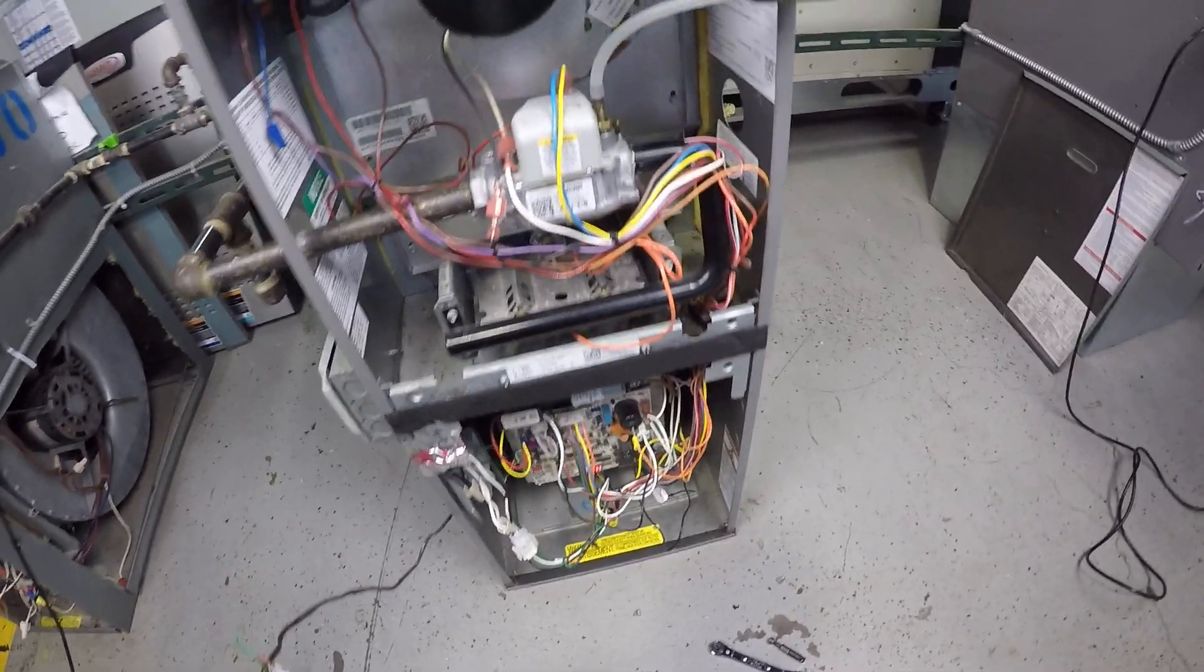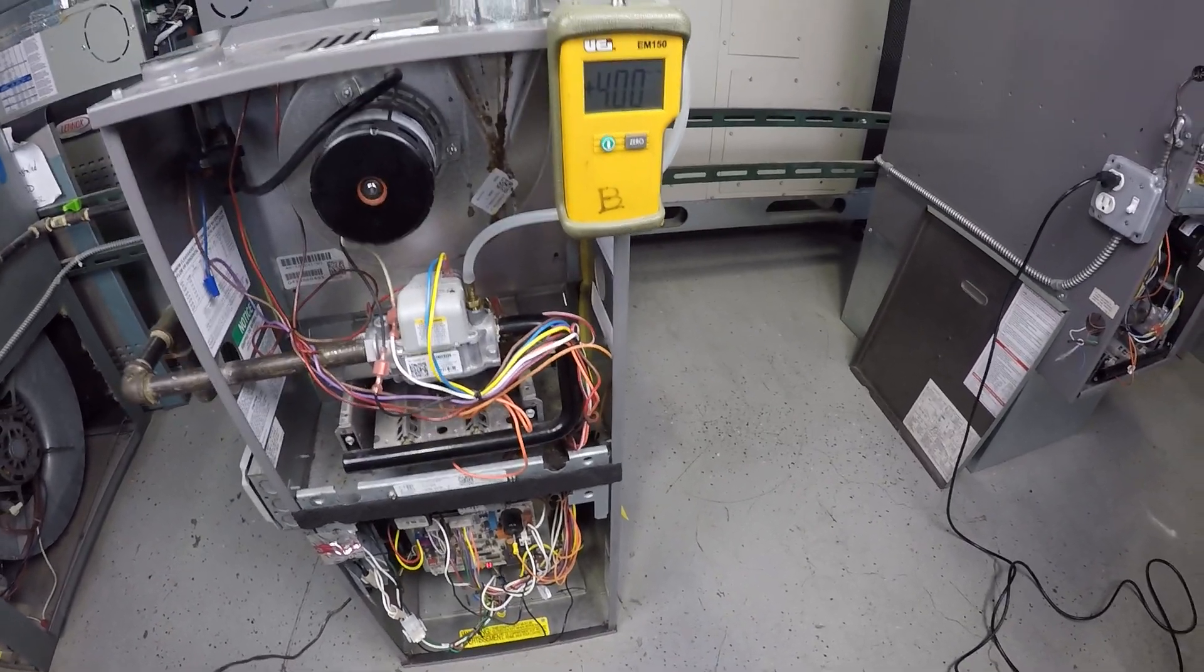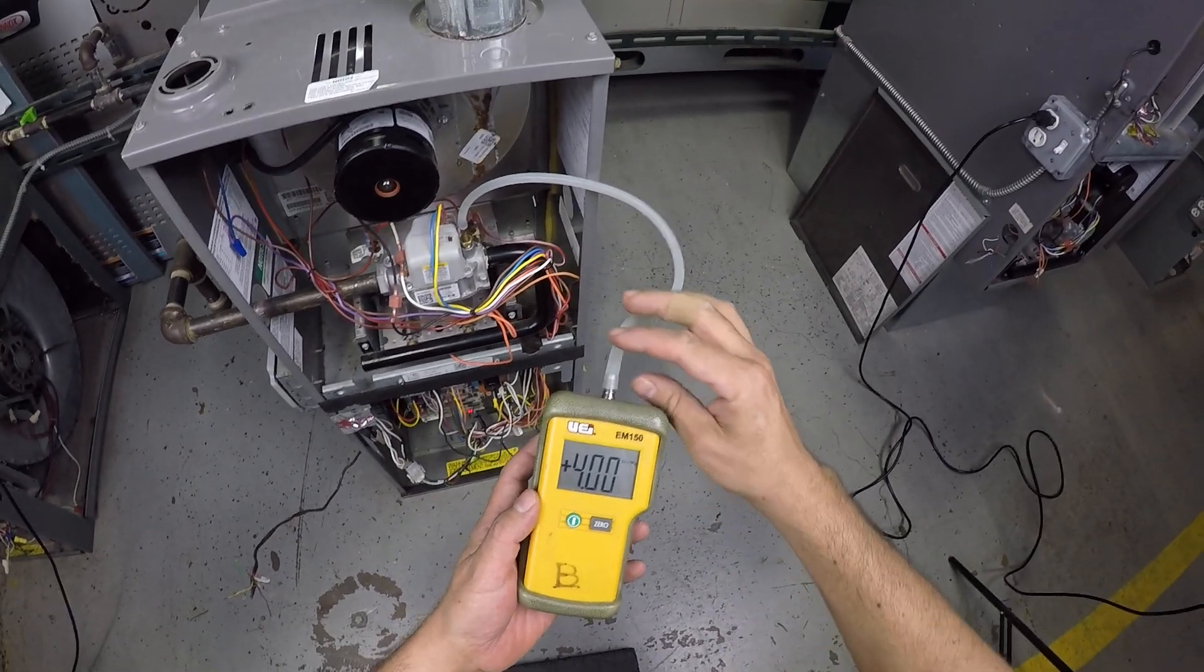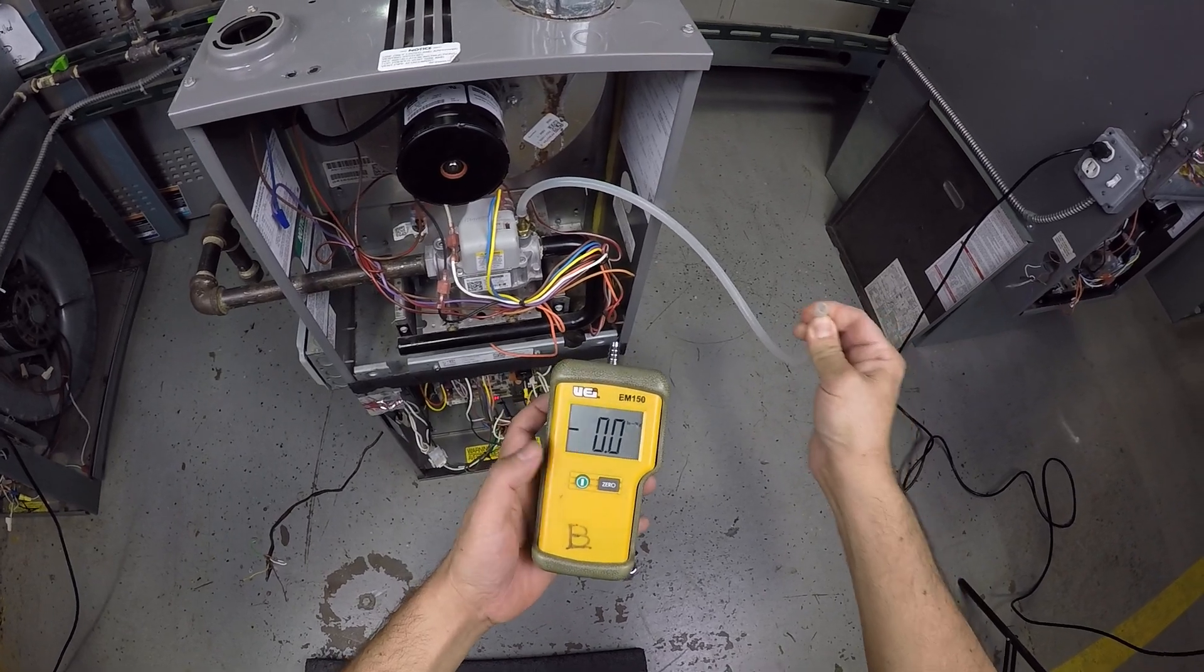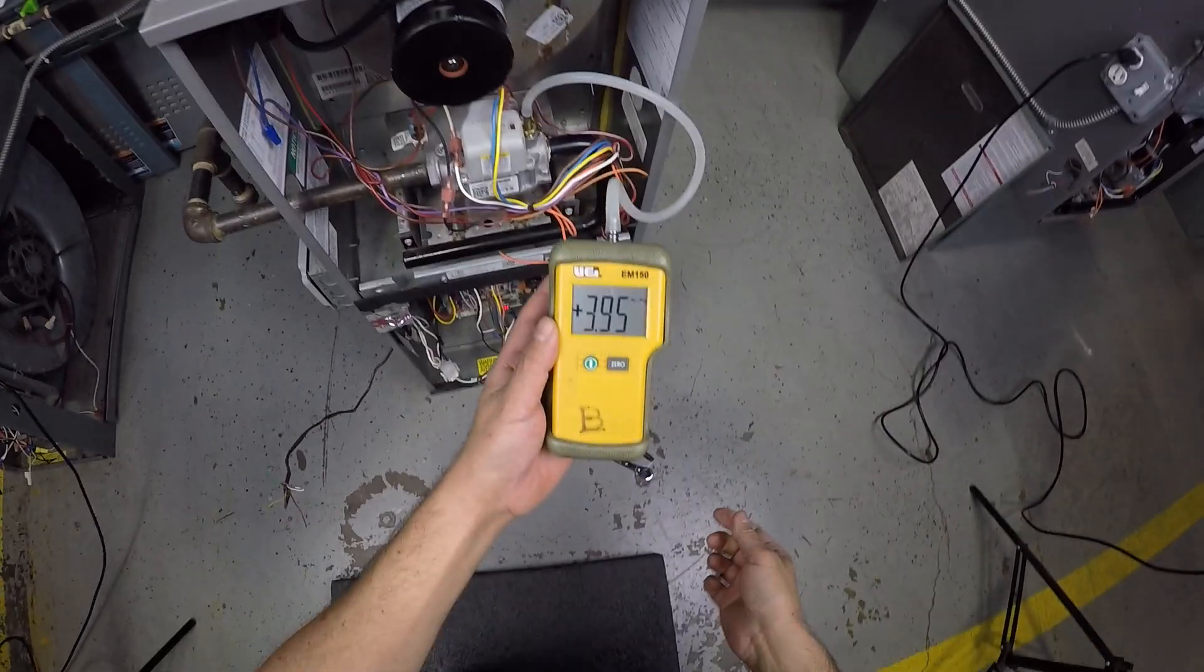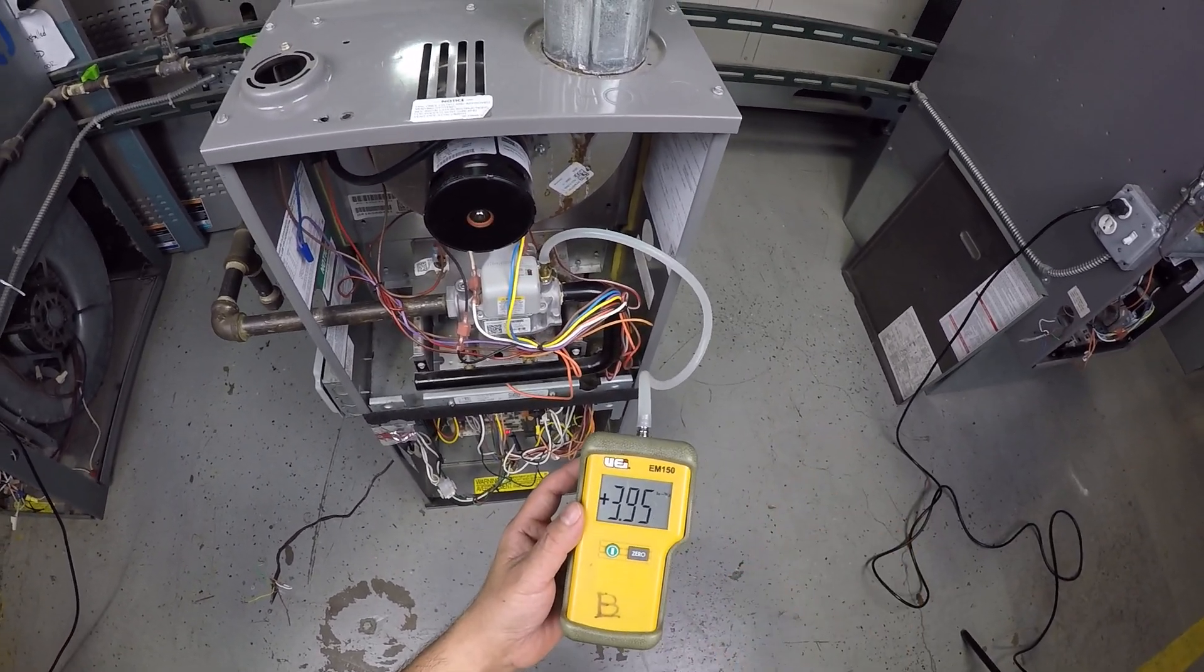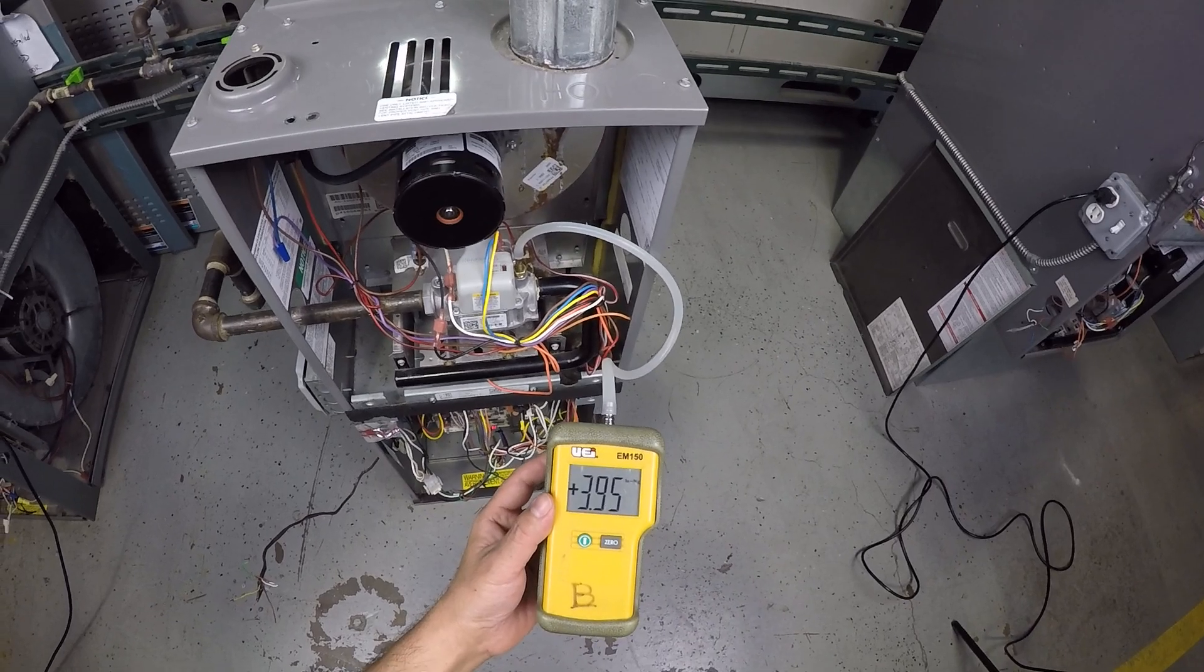Burner's on. And now, let's check the gas pressure. My gas pressure is four inches water column. Once again, what I like to do is remove the connection, make sure it's zero, and connect it back. This is what I normally like to do. It went down a little bit. Normally, the gas pressure going to the manifold is 3.5. We've got 3.9. So, we can probably adjust it. But that's going to be a different video. This is just how to check the pressure in and out of the gas valve.